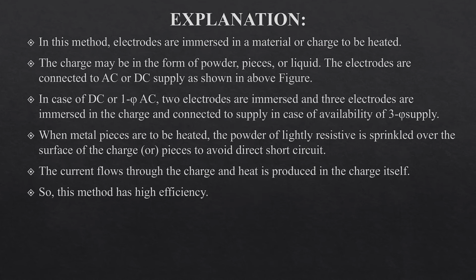When metal pieces are to be heated, powder of high resistivity is sprinkled over the surface of the charge to avoid direct short circuit. Whenever the current flows through the charge, heat is produced in the charge itself. This method has the highest efficiency. As the heat is directly transferred to the charge, this method is called direct resistance heating. As the current in this case is not variable, automatic temperature control is not possible. This method of heating is employed in salt bath furnaces and electrode boilers for water heating.